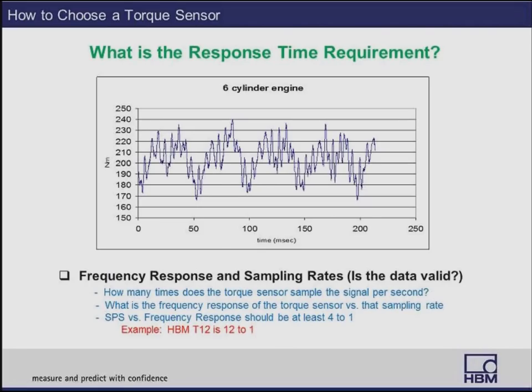What is the response time requirement of your application? Modern torque sensors can be viewed as rotating accelerometers, capable of measuring torsional noise or vibration. It's important to know if your torque sensor has sufficient response time and sampling rate to capture these torsional vibrations. An example is the HBM T12, which samples at 72,000 samples per second. To avoid aliasing, the ratio between sampling rate and frequency response should be at least 4:1 — the T12 achieves 12:1. If response time and sampling rate are important, make sure your torque sensor can accommodate that measurement.